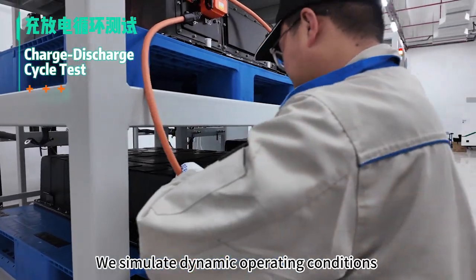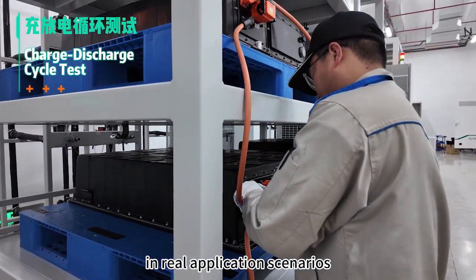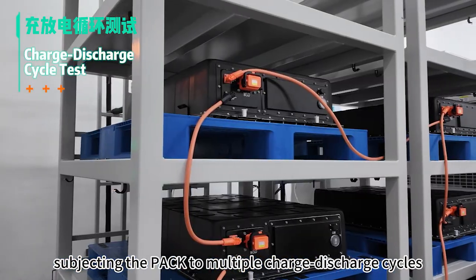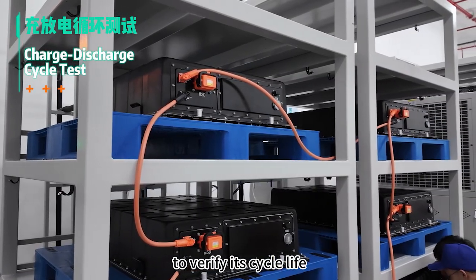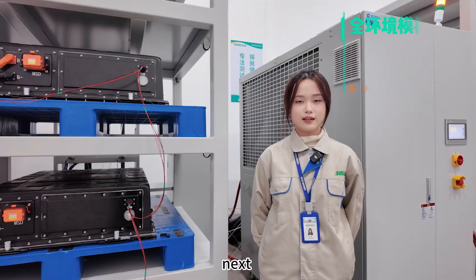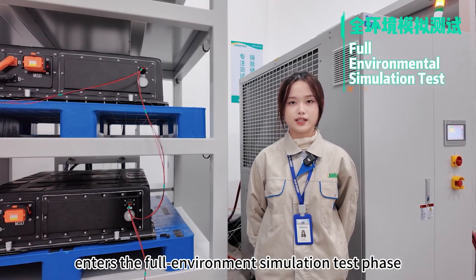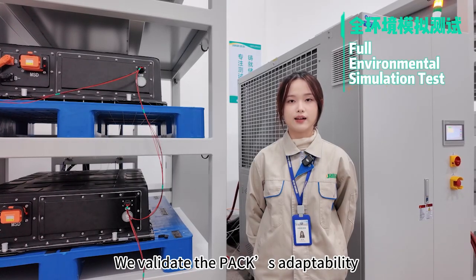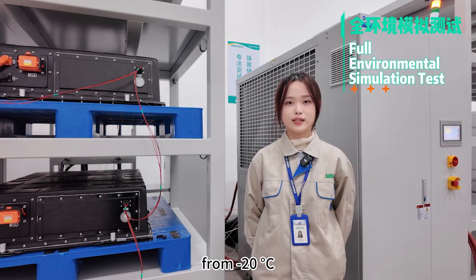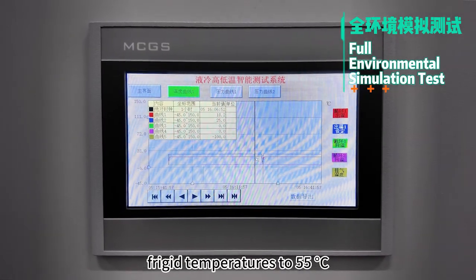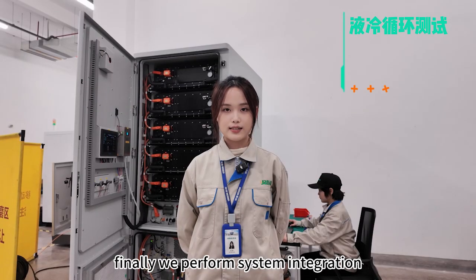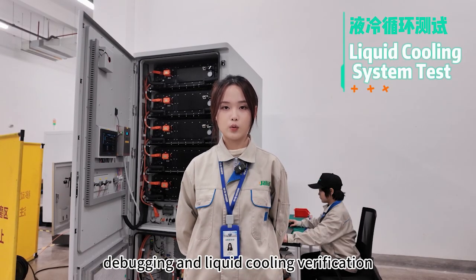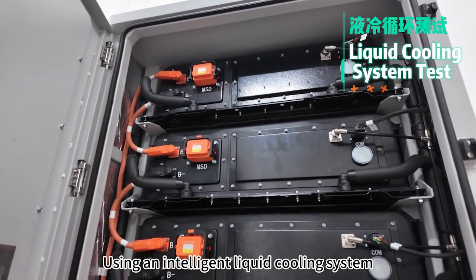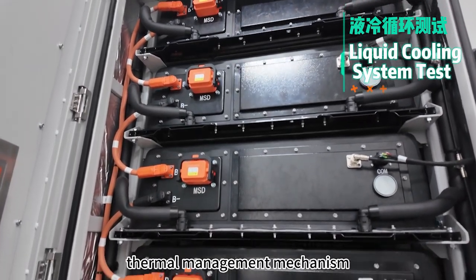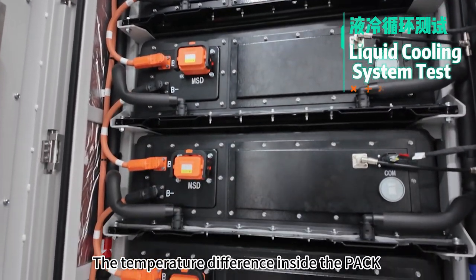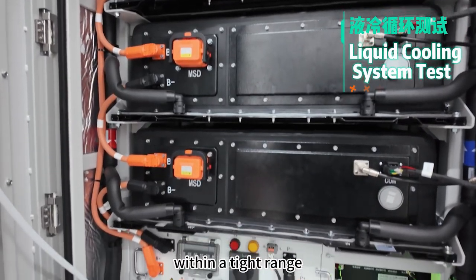We simulate dynamic operating conditions in real application scenarios, subjecting the pack to multiple charge-discharge cycles to verify its cycle life, performance, and stability. Next, the pack enters the full environment simulation test phase. We validate the pack's adaptability across extreme conditions, from -20 degrees Celsius frigid temperatures to 55 degrees Celsius scorching heat. Finally, we perform system integration debugging and liquid cooling verification. Using an intelligent liquid cooling system, we establish a complete thermal management mechanism. The temperature difference inside the pack is strictly controlled within a tight range.